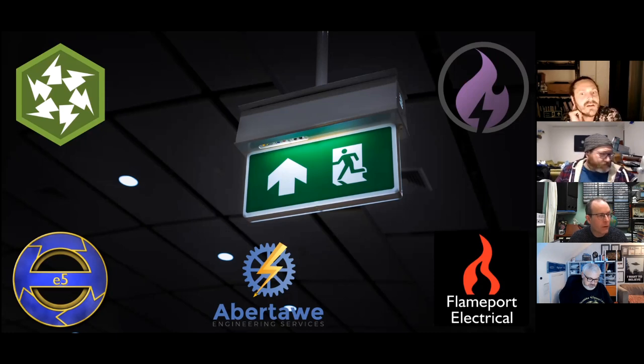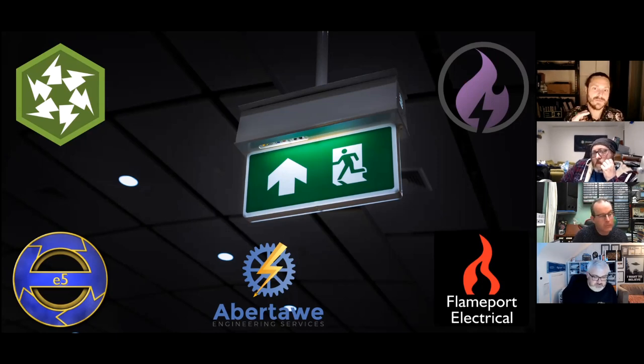Obviously, with segregation, we have to make sure we've got the difference between LV, ELV, and then fire alarm, which 528 of BS 7671 covers. Yeah, it does. So you're supposed to have different segregation, and there's many reasons for that. Depending what ELV cables there are, we have installed fire alarm cables on, say, tray work that has ELV cables, as long as we keep them as far away as we can. And we just make note of it, and, you know, the designer agrees.